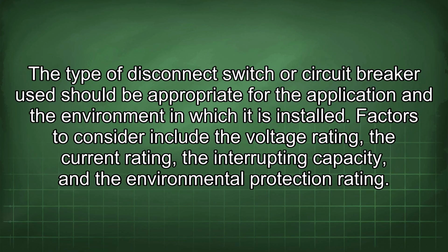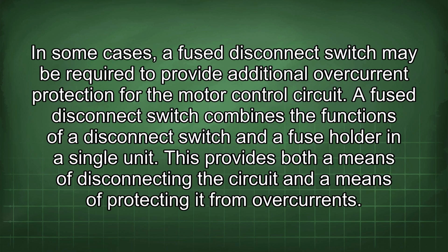The type of disconnect switch or circuit breaker used should be appropriate for the application and the environment in which it is installed. Factors to consider include the voltage rating, the current rating, the interrupting capacity, and the environmental protection rating. In some cases, a fused disconnect switch may be required to provide additional overcurrent protection for the motor control circuit. A fused disconnect switch combines the functions of a disconnect switch and a fuse holder in a single unit. This provides both a means of disconnecting the circuit and a means of protecting it from overcurrents.